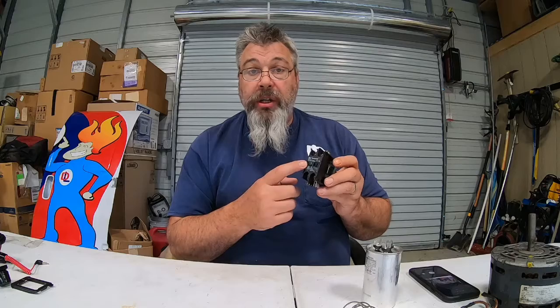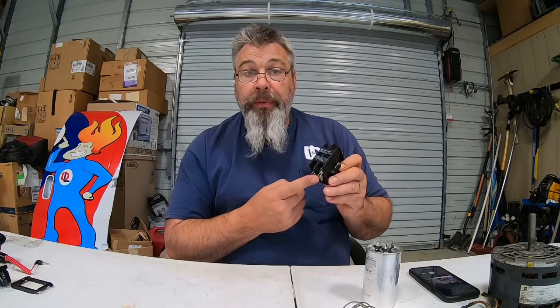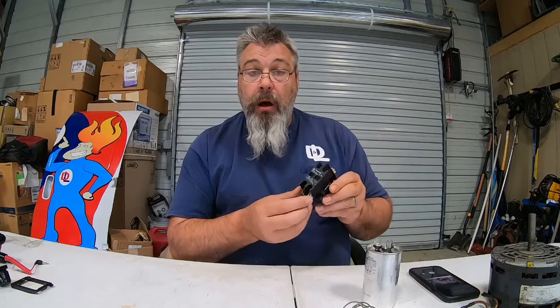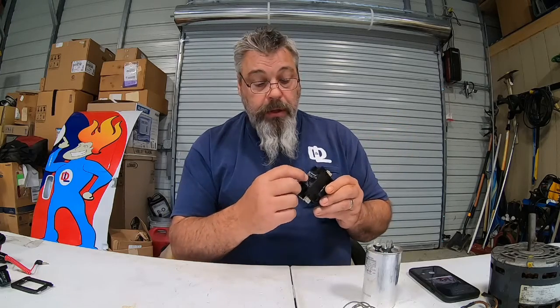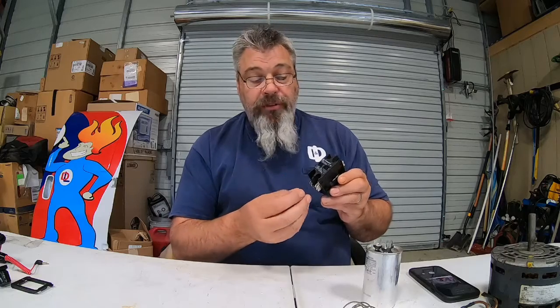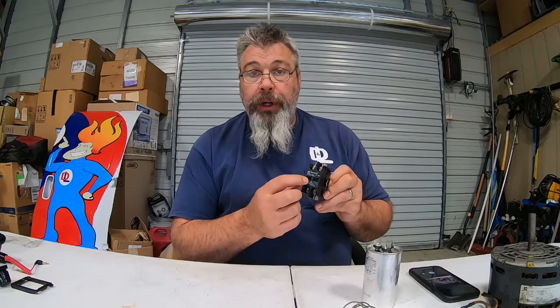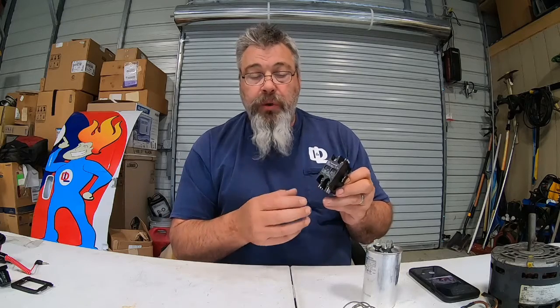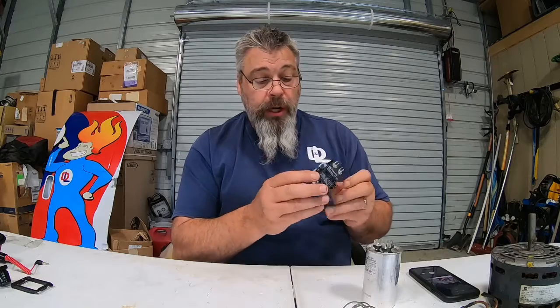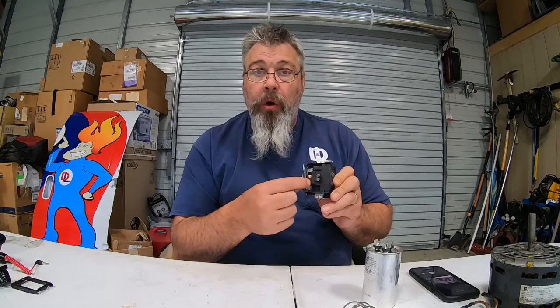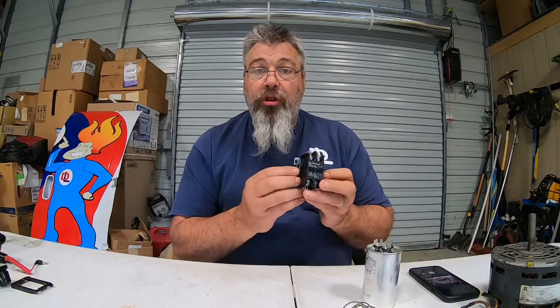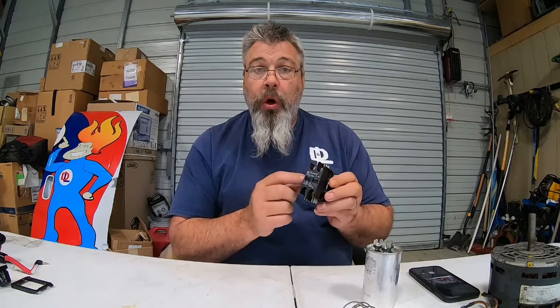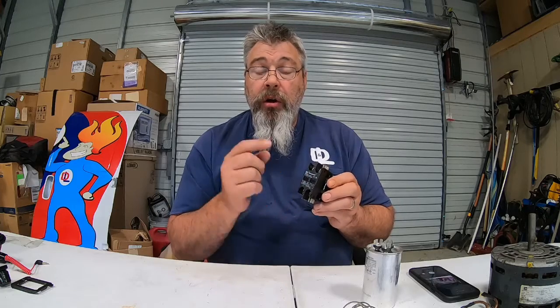The next component that we have inside here is called a contactor. This contactor basically takes high voltage and brings it in the bottom and allows it to come out the top. Now, this acts like a light switch. It pulls in and out, makes the contact, and allows that high voltage to go through. So when we have no call, the contactor is out. It's not pulled in. What we consider pulled in means that it has been energized. We check these with ohms resistance from bottom to top. We also check that it's got a little coil inside here. Inside that coil, these terminals on the left and right here are your low voltage terminals. This is what energizes your contactor from your thermostat.